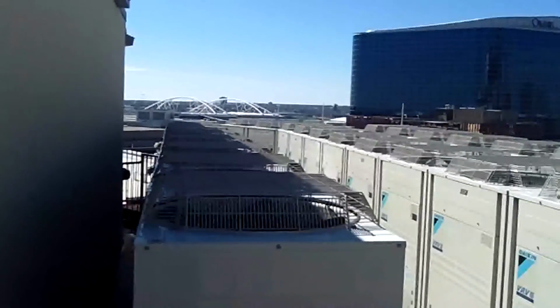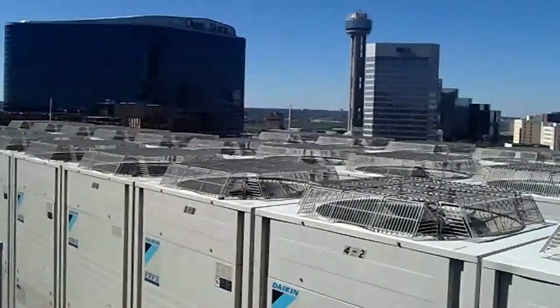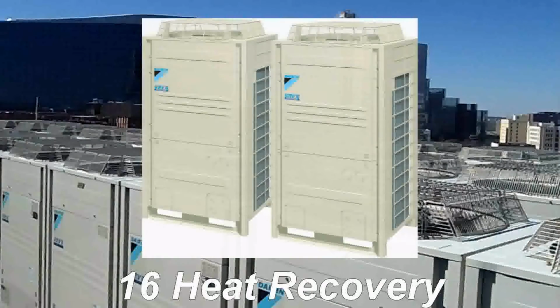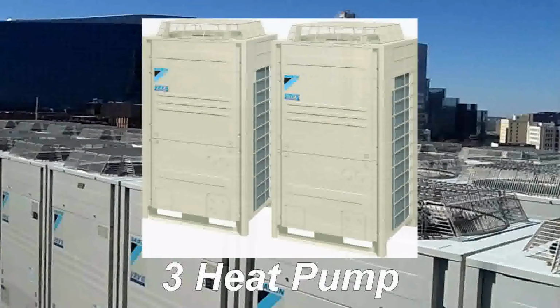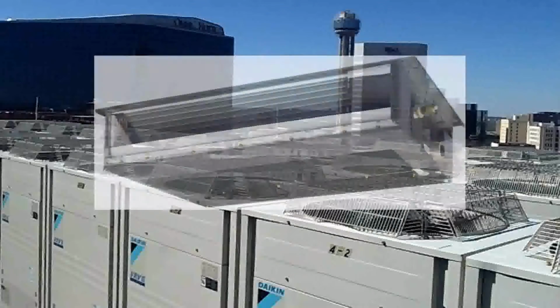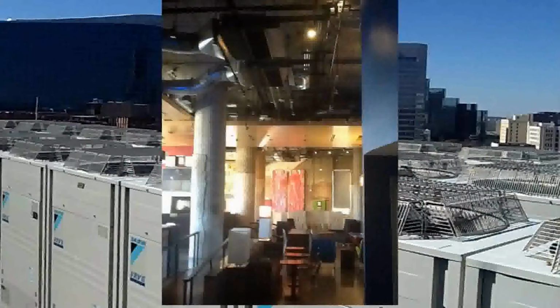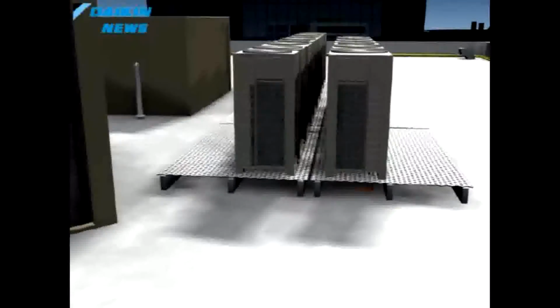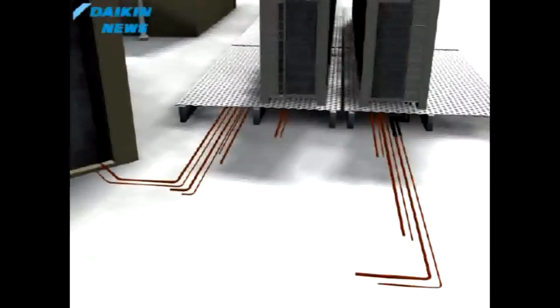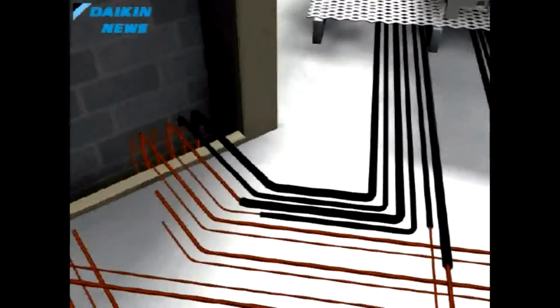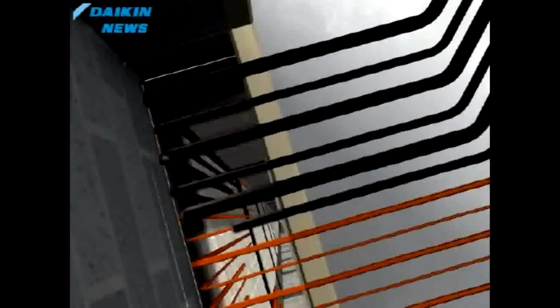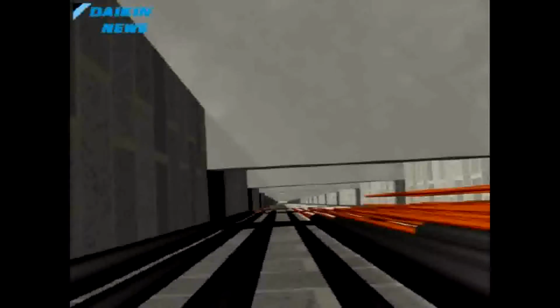results. On the roof, there are 19 condensing units, 16 that are heat recovery, and 3 that are heat pump. They service 240 fan coil units placed in the rooms, common areas, and meeting rooms. The refrigerant that is used to heat and cool the space starts off in the roof at the condensing unit and is run down through the building in copper tubing to each fan coil unit.